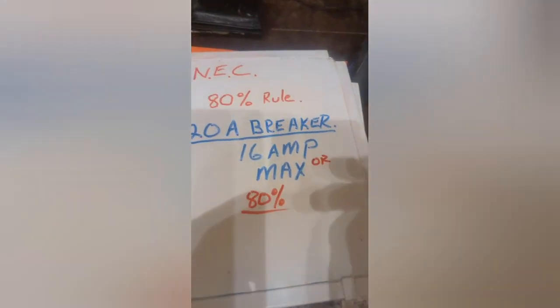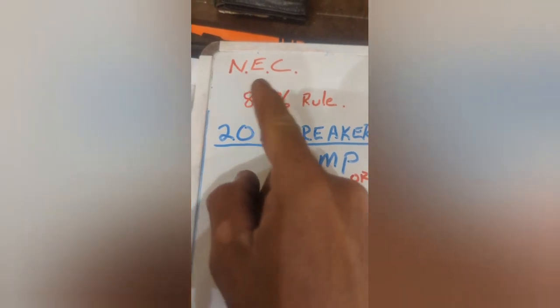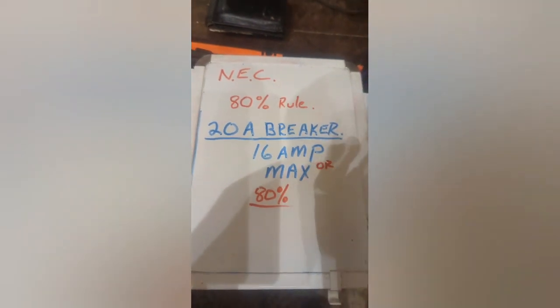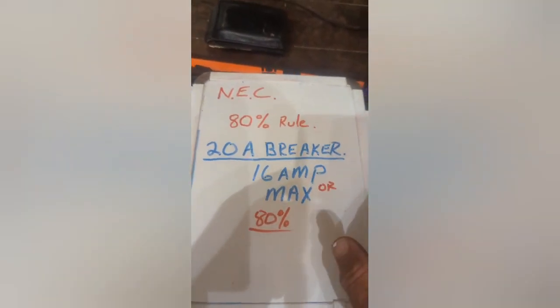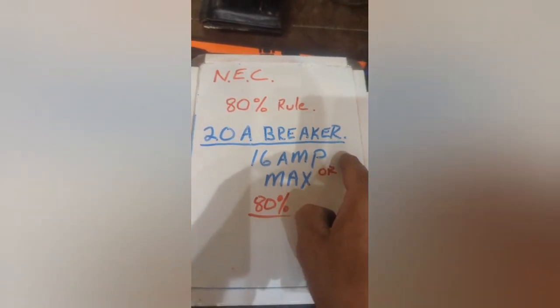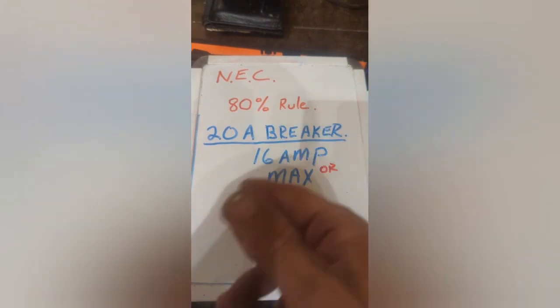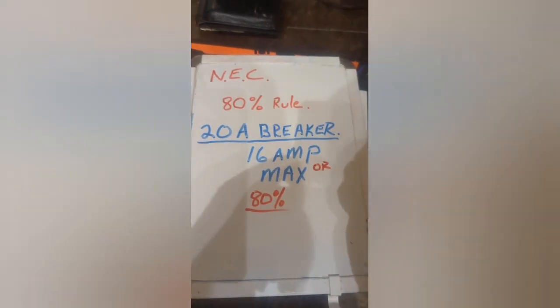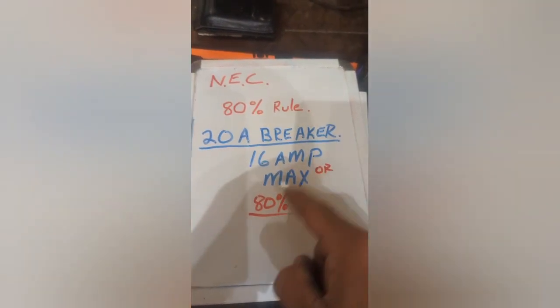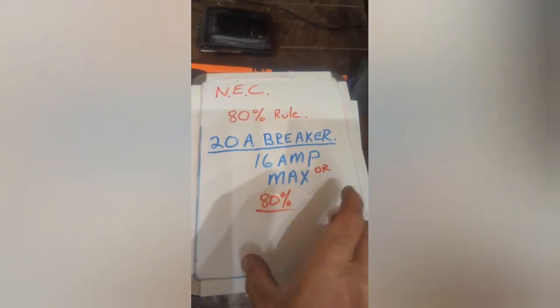Alright, folks. So there's this little place called the NEC or the national electrical code. And there's this thing called the 80% rule. And this is going to apply to your breakers. So it's real simple. If you have a 20 amp breaker, you should only be running at 80% of that capacity of that breaker. So in other words, your continuous load, which is described as three hours or more, should be at 16 amp max or 80%.